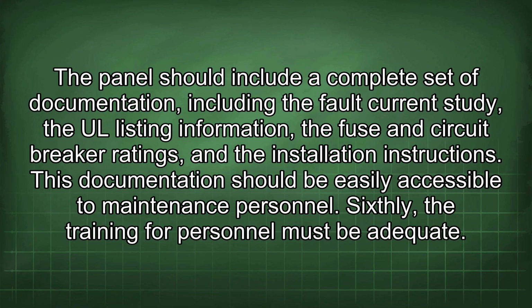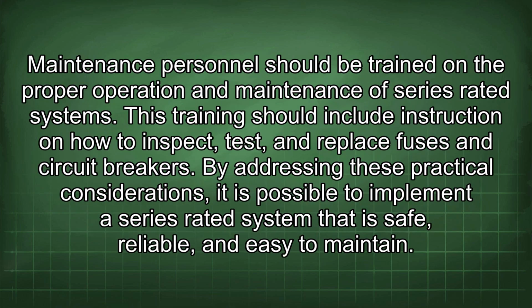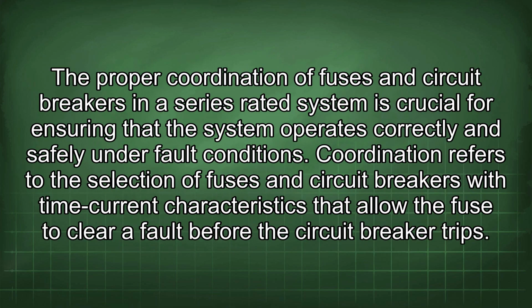Sixthly, the training for personnel must be adequate. Maintenance personnel should be trained on the proper operation and maintenance of series-rated systems. This training should include instruction on how to inspect, test, and replace fuses and circuit breakers. By addressing these practical considerations, it is possible to implement a series-rated system that is safe, reliable, and easy to maintain. The proper coordination of fuses and circuit breakers in a series-rated system is crucial for ensuring that the system operates correctly and safely under fault conditions.